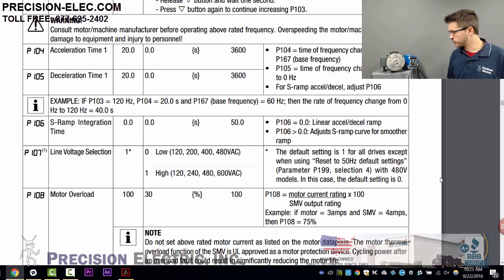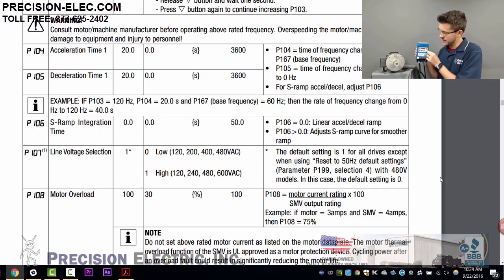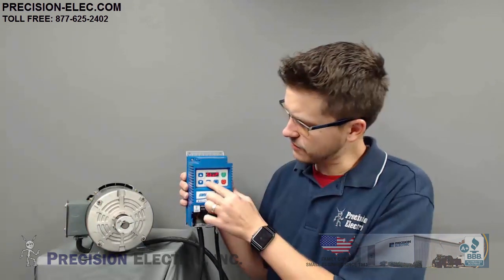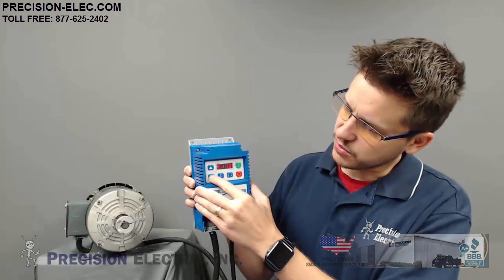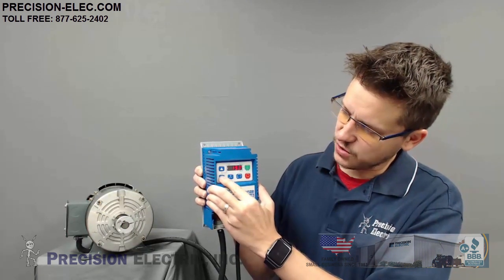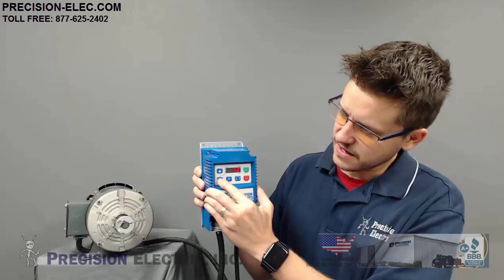Acceleration time and deceleration time — parameters 104 and 105. As we were talking about before, it took a long time to start and it takes a while to stop. If I go into the menu and go to parameter 104 — this is my acceleration — and hold down the down arrow key, I can bring that down.